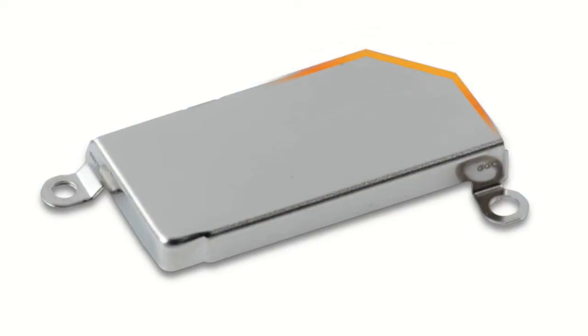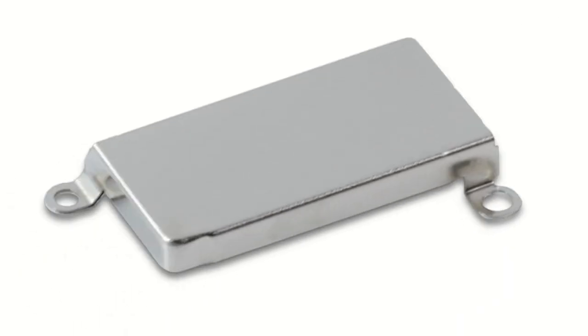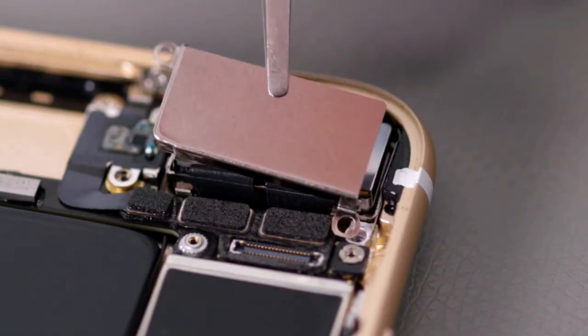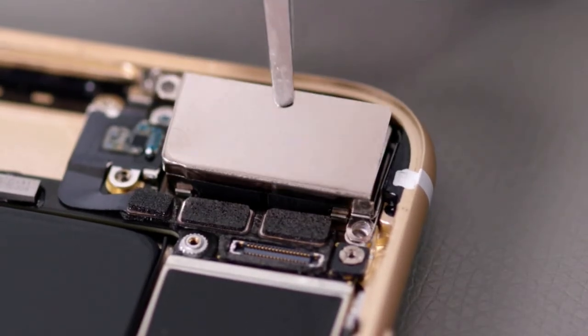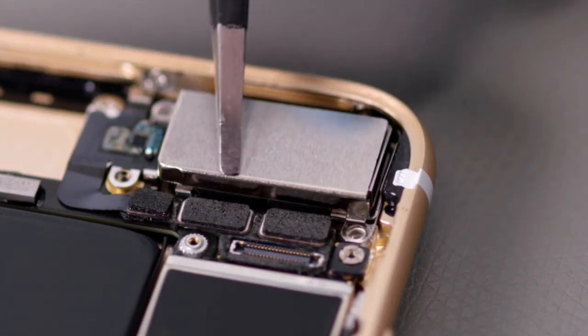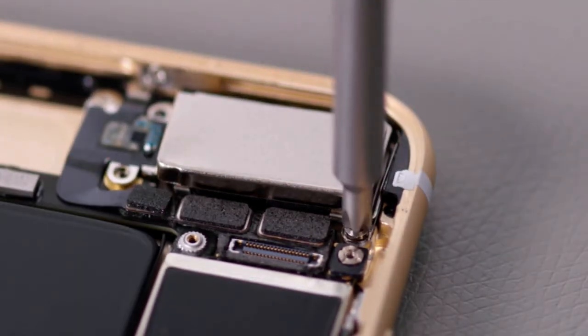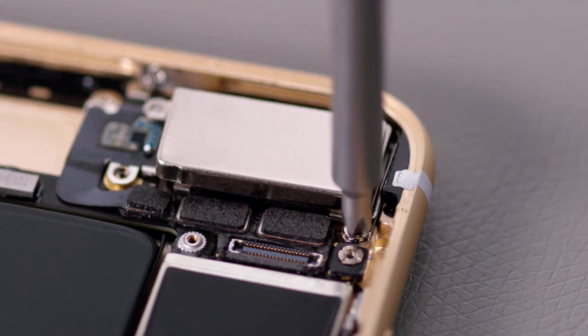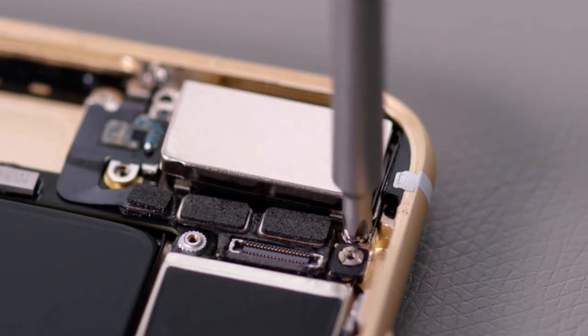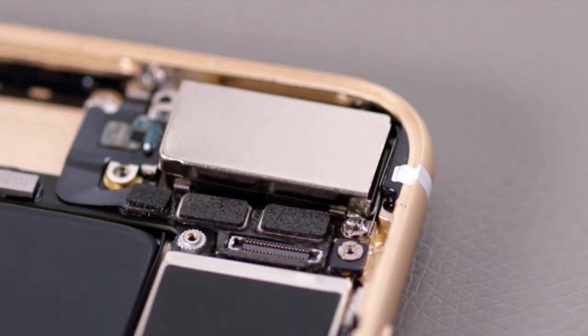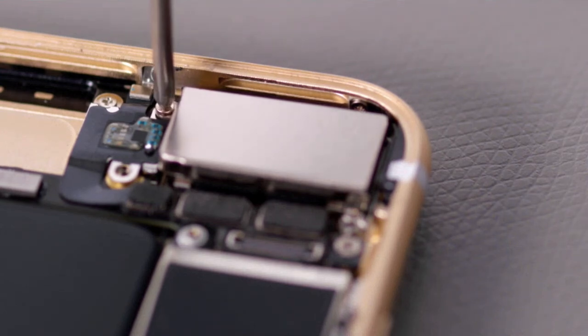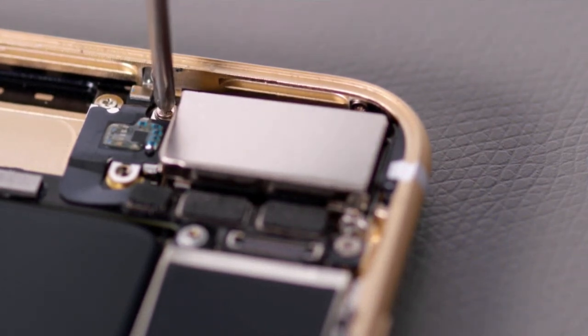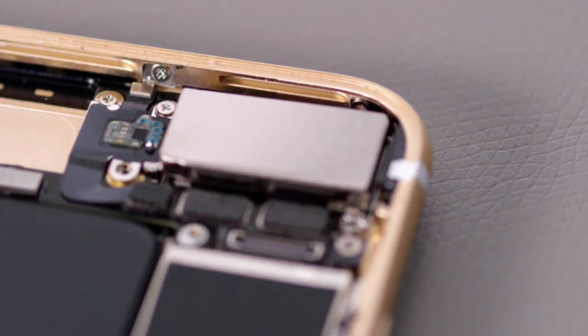Check the camera cowling. If it has the cut in the upper right corner, replace it. Install the camera cowling. Use the green torque driver and super screw bit to install a new super screw on the lower right corner of the camera cowling. Use the green torque driver and JCIS bit to install a new crosshead screw on the upper left corner of the camera cowling.